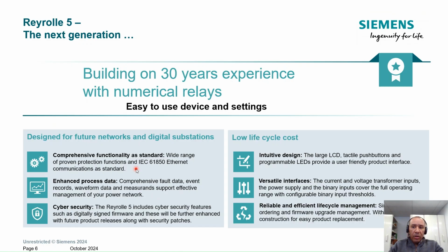You don't pay more for protection functions; all the protection functions come as standard. Also, communication: all the communication protocols come as standard. It's like 61850, DNP3, and also Modbus, either serial or TCP/IP. Enhanced process data: this device gives you fault data, event records, and traces, that is the waveform, and you just download this information from the relay using the software that we call Reydisp Manager version 2.